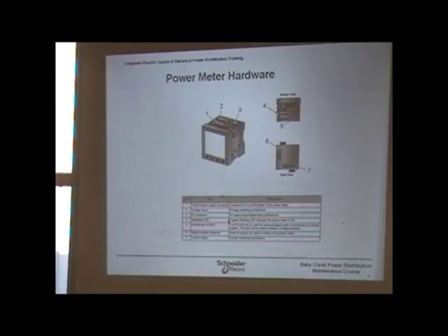But it takes power directly, I was telling you, directly right off the bus. So if it's 480, it'll take 480, so you don't need PTs. So it makes it very simple, very easy to go in there. Line 1, line 2, line 3, neutral, and ground.